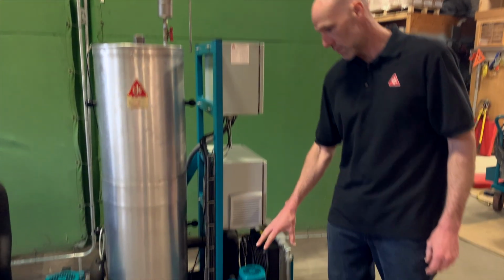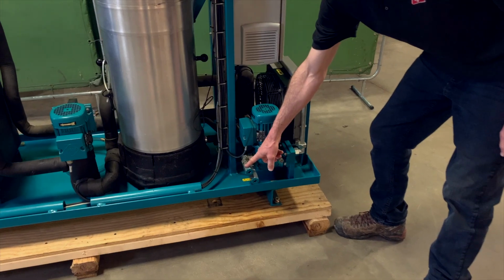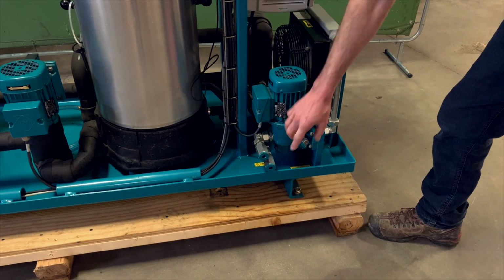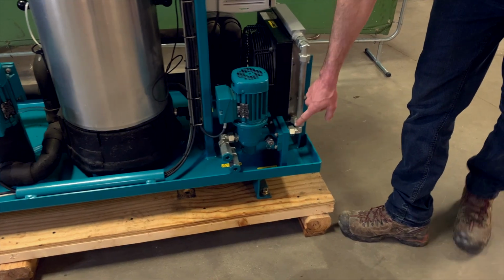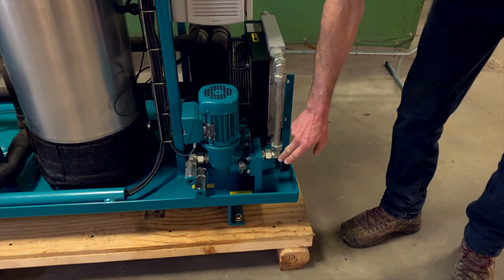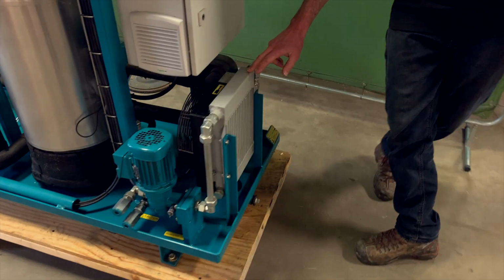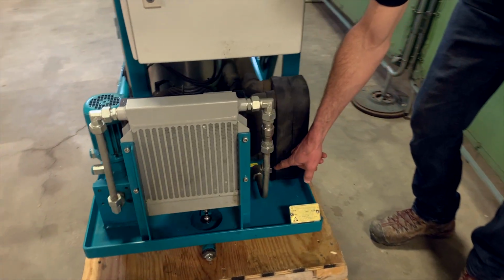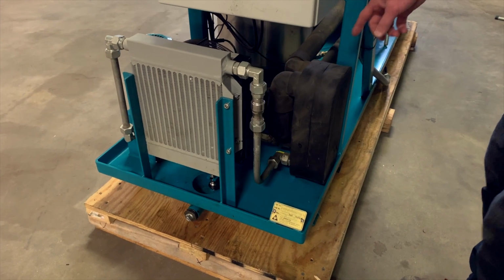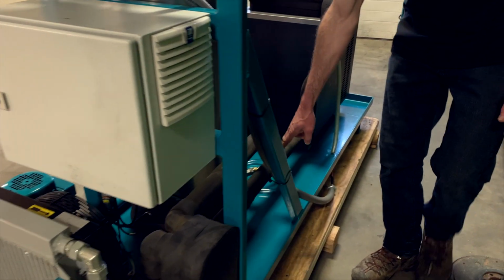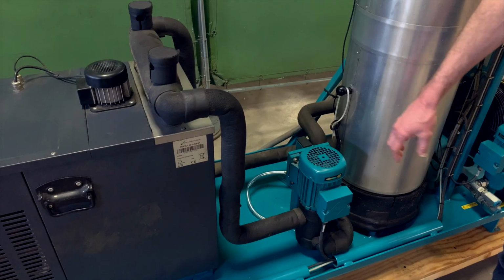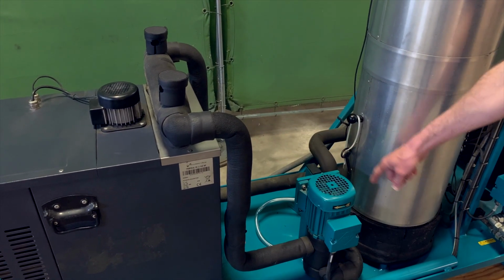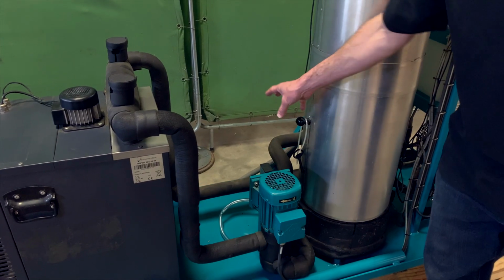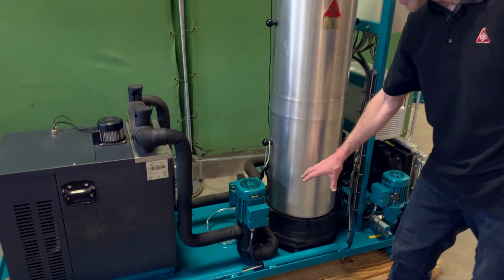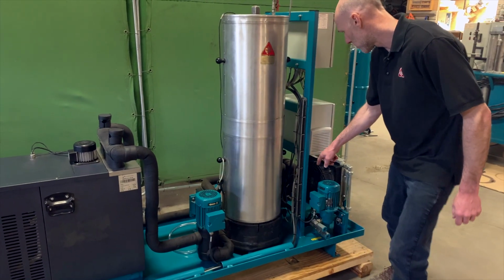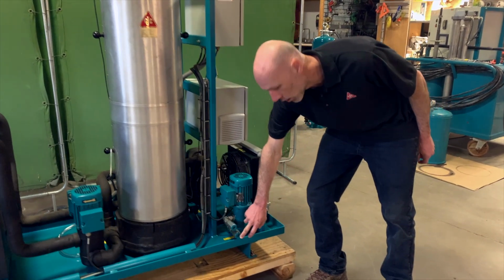So we'll start with the supply circuit. Down here is our inlet port and our inlet pump. That moves the oil past the pre-filter sample point. That comes into our fan cooler. Then it comes into our heat exchanger, out the other side of the heat exchanger, and then it comes through to our chiller assembly. The circulating pump moves the oil through the chiller and the filters in a loop, while the supply pump pushes a small amount of oil completely through the system. That comes to the outlet, back through the heat exchanger, and then to your outlet port back to the system.